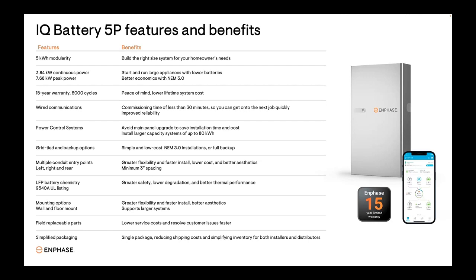And the peak power is actually also higher. The peak power of the 5P is 200% of the continuous power, whereas with the 10T it was only 150% of continuous. That allows the 5P to be very capable of starting large appliances that have a demand spike or starting surge when they start up, like air conditioners, some heat pumps, well pumps, etc.